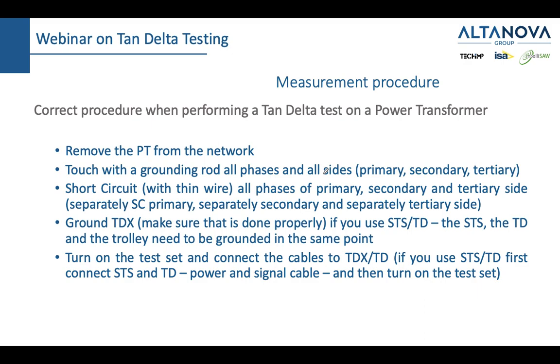The third step is short circuit. This is very important. We should short circuit fully the primary side, phases ABC, the secondary side separately, ABC, and if you have also the tertiary side. You should do that, you will see why, and when you do that, you should also correctly ground your testing equipment. Correctly ground means that you ground the testing equipment at the same grounding point where your transformer is grounded. So you shouldn't have two different points of grounding, otherwise the current can close in a different loop and you might get bad results.